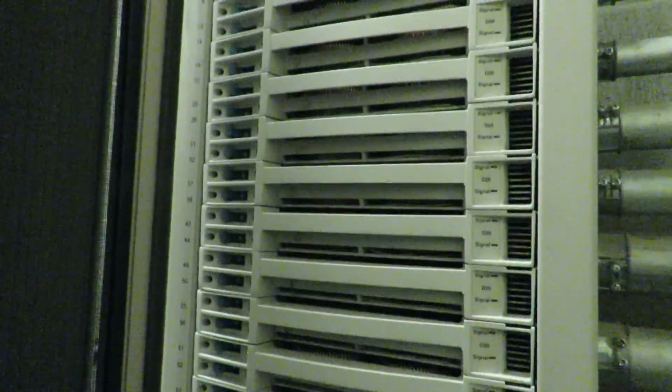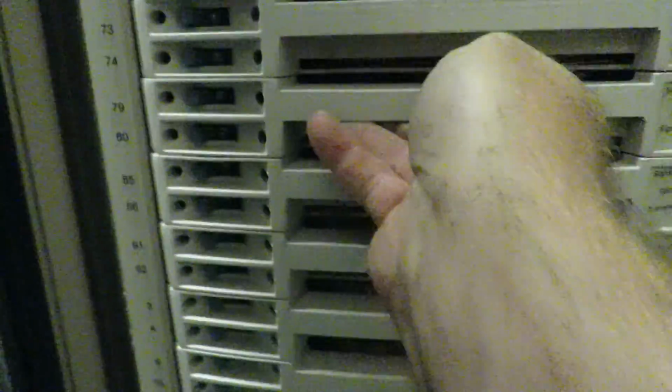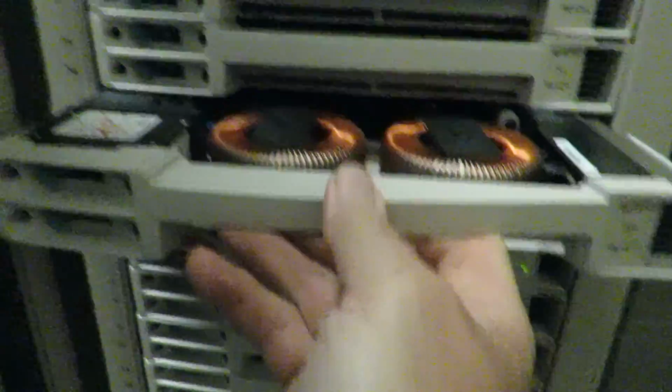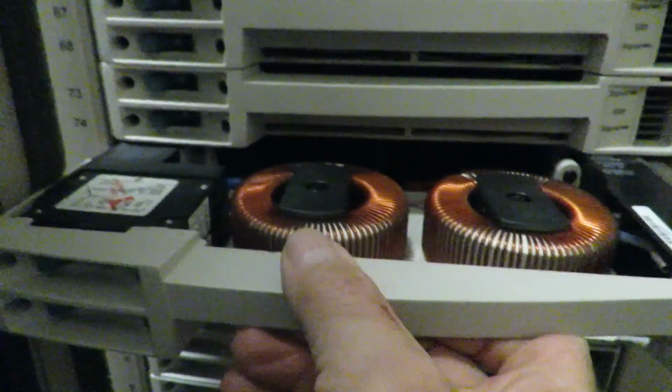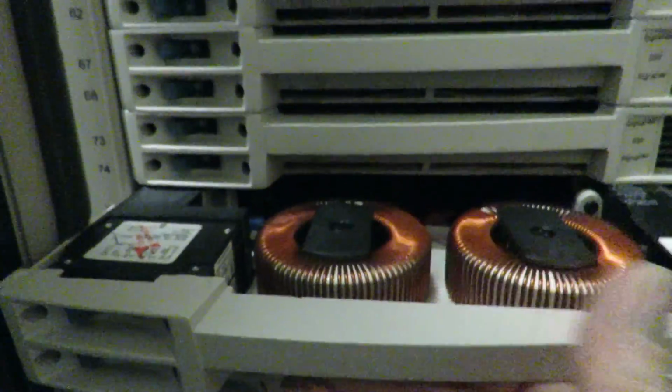It may be hard to hear me with the fan noise, but you open up this cabinet and you see all these individual little modules, and the modules can be pulled out, and you see there are two copper coils in there. That means that each one of these modules controls two separate circuits. So there are 48 modules in all, which means that we have 96 dimmers throughout the theater.